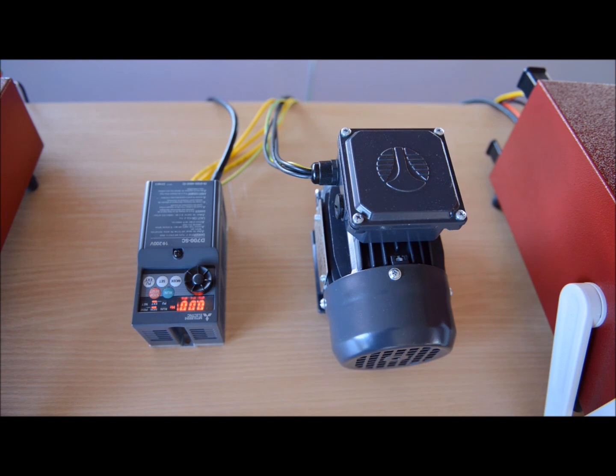So let's move on to setting up the analyzer, looking at some waveforms. Let's initially turn on the device. Turn that on. Standard frequency default, well, here is 31 Hz. So I'm going to leave it at that, and we'll set up the output in order to measure a 31 Hz motor frequency, remembering we have an approximate 7 kHz switching frequency.